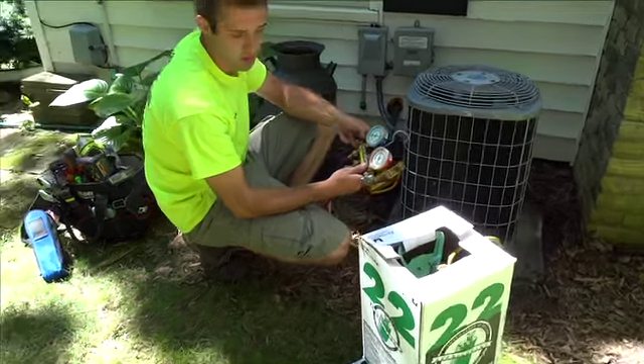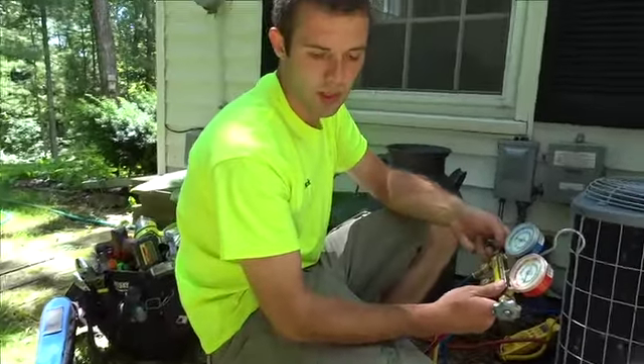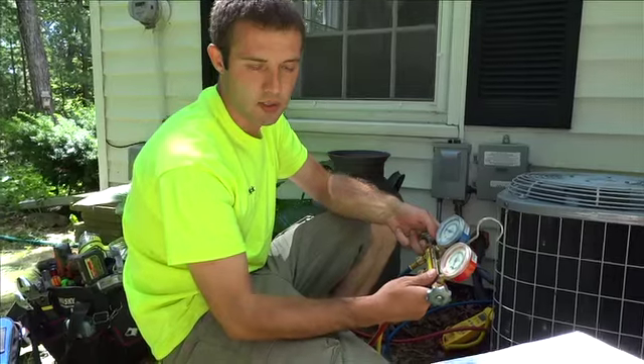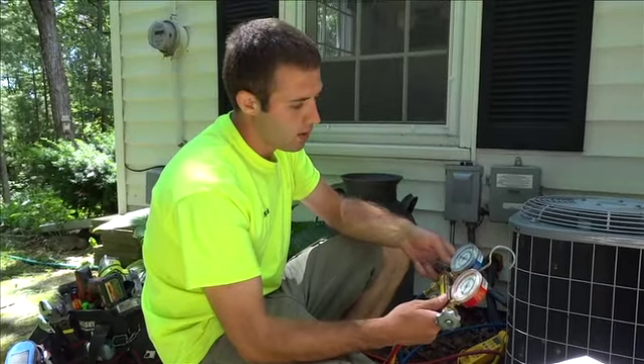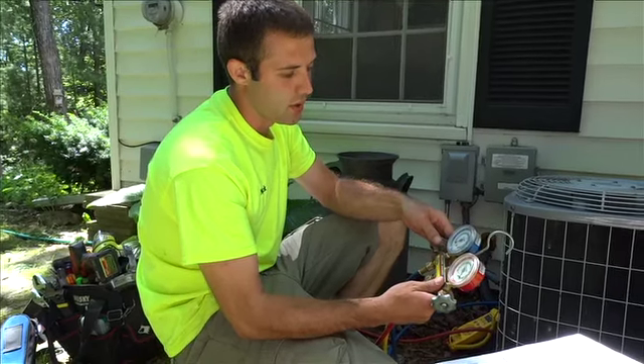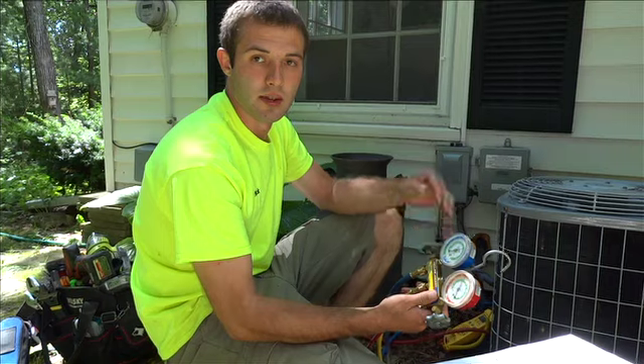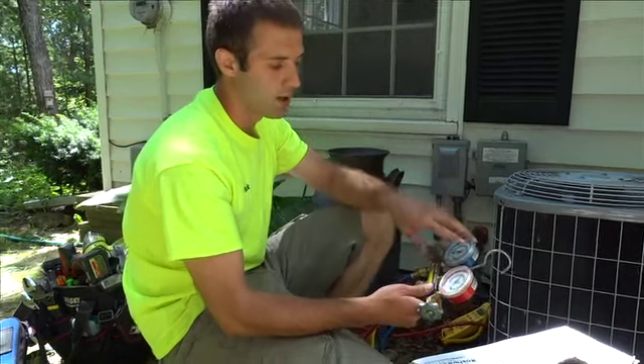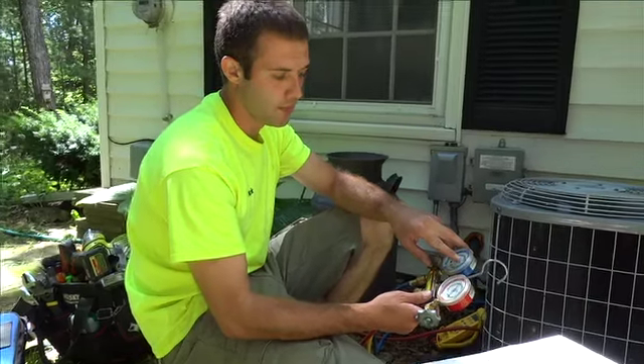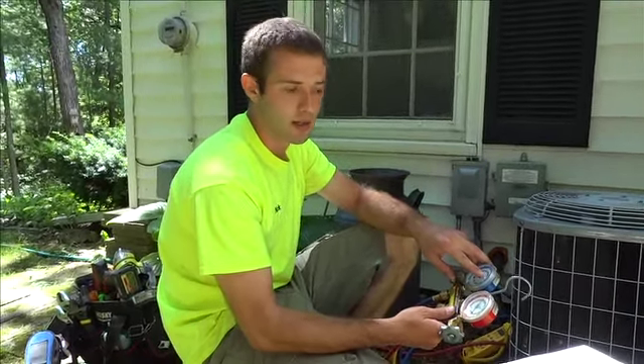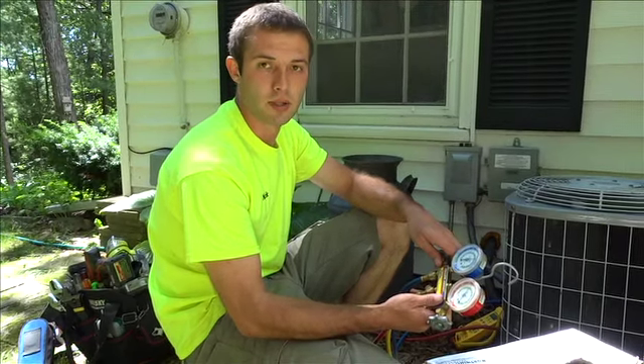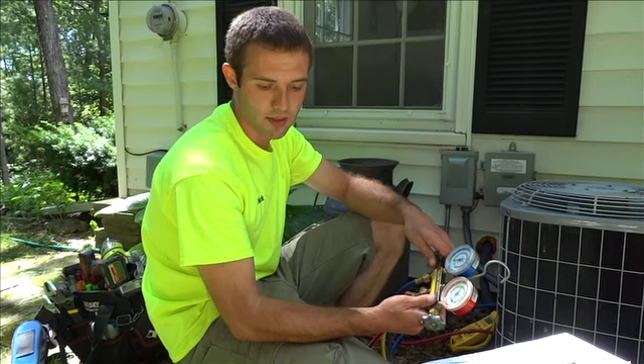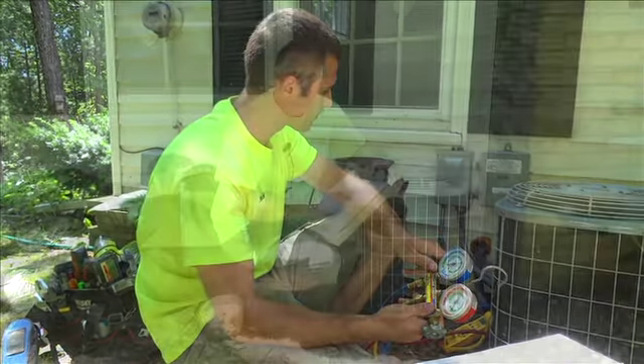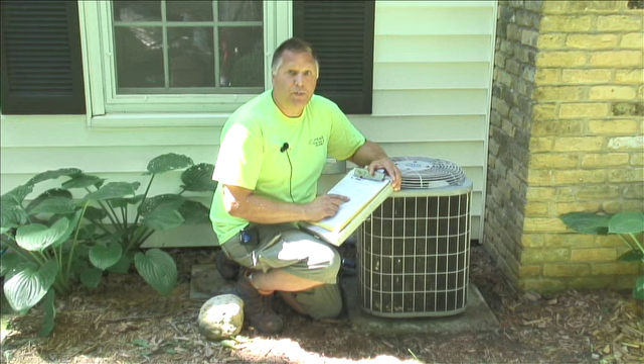Every time we add refrigerant, we weigh it out, so we know exactly how much refrigerant we are putting in. Every time you add refrigerant, it takes about 5 to 10 minutes to actually even out with our temperature and our gauge temperature. So it's a little bit of a process, and to get it done right takes a little time. So, go through our 11-point checklist, that pretty much wraps up your tune and check of your condensing unit, and your air conditioner is good to go for the summer.